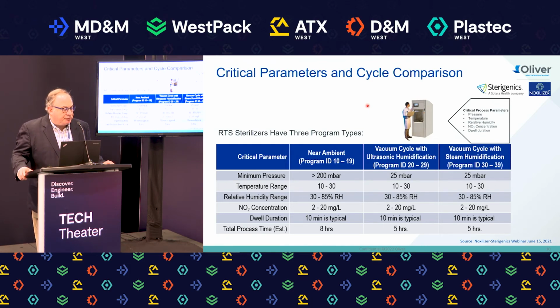There are 3 programs that we employ for NO2 sterilization. The first one is a near ambient program, and these are the process parameters that we typically use. Greater than 200 millibar, temperature range 10 to 30, 30 to 85% RH, 2 to 20 mg per liter. The next one employs a vacuum cycle using ultrasonic humidification to administer the humidity to the chamber. And the third one uses steam humidification to introduce humidity to the chamber.